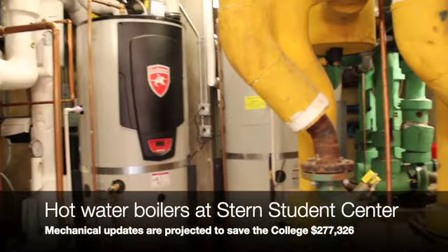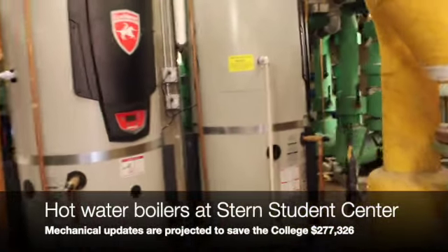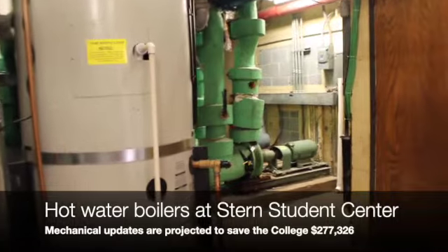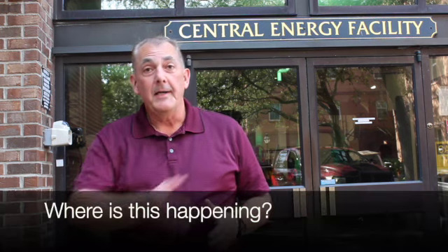We decentralized a good part of our steam system in doing this too. So we're not providing steam to the campus like we did at one time. We were providing steam to 12 buildings, and now we're providing steam to 4 buildings. So those buildings that came off, those 8, are now provided heating hot water and domestic hot water through boilers. Heating hot water is used for heating the building, and primarily for dehumidification control. It's being made right here in the Central Energy Plant.